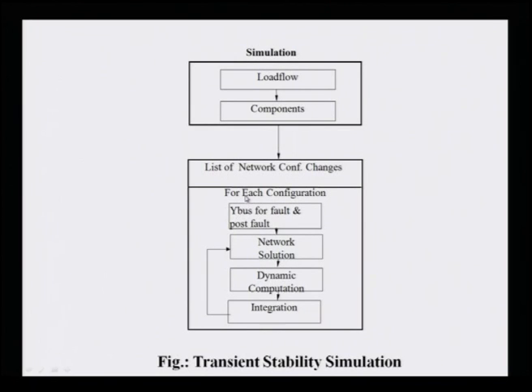For each configuration, we have to decide the network states: pre-disturbance, during disturbance, and post-disturbance. So we have three categories: pre-fault conditions of the network, during fault when the fault is persisting, and post fault when the fault is cleared.